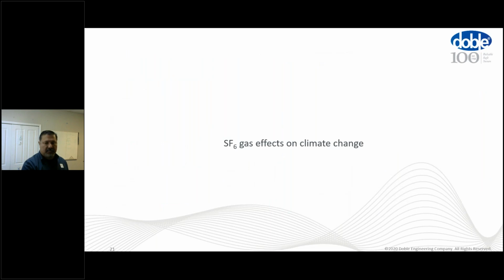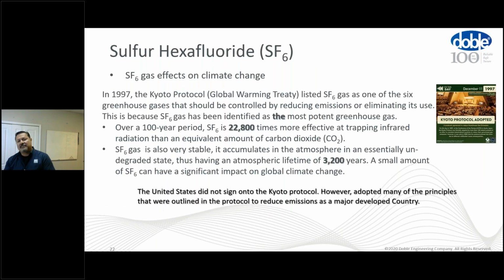Its effects on climate change. In 1997, the Kyoto Protocol, called the Global Warming Treaty, listed SF6 as one of the 6 greenhouse gases that should be controlled by reducing or eliminating its use. In other words, it was found to be one of the most potent greenhouse gases, with over a 100 year period, SF6 at 22,800 times more effective at trapping infrared radiation than the equivalent of carbon dioxide. CO2 is how we measure our greenhouse gases, so 1 pound of SF6 would be 22,800 pounds of CO2.